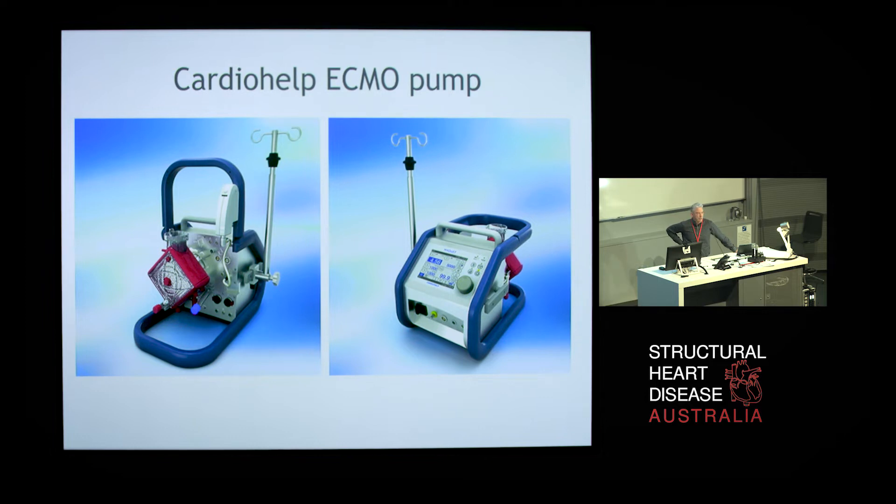The heart and lung machines have obviously come a long way as well. This is the Cardiohelp pump that we use for ECMO cases. It weighs about 10 kilos. This little red box here is the oxygenator. There's a centrifugal pump integrated between the oxygenator and the pump, with about a two-hour battery backup and integrated hematocrit saturation monitoring. It's a very sensitive and sophisticated piece of equipment, and the circuit is actually rated for 30 days of continuous use, so it should be a single-use item for these cases.